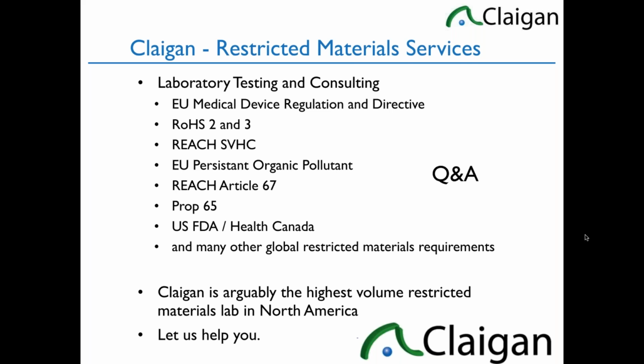Another great question. Is the percent by weight limited to just the invasive patient contact portion of the device, or does it refer to the whole device? It is not well explained. However, the way they wrote "or parts therein," it looks like they are discussing the material in contact. So it's percent by weight of the material in contact as opposed to the device. There should be more guidance on it, but the most reasonable reading is the percentage of the material in contact with the invasive or gas or liquid.